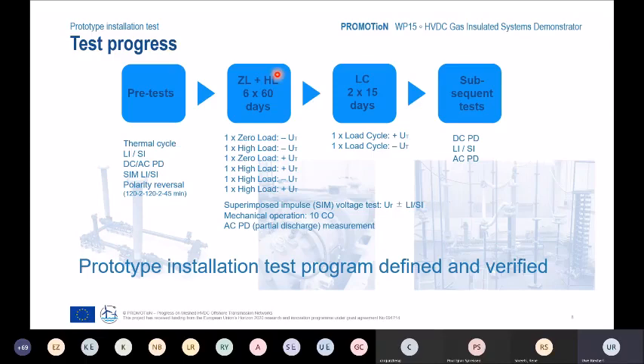And we have defined in total 6 load cycles without any current or with current, different DC polarities, and each cycle has a duration of 60 days. So in total, we cover nearly 1 year with these 60-day cycles. 60 days was chosen to cover the time required to reach the DC steady state for the installation. We have added 1 cycle with load cycle tests, specially defined from real experience from an offshore platform. And before starting the test, we have defined some pre-tests, including polarity reversal tests.